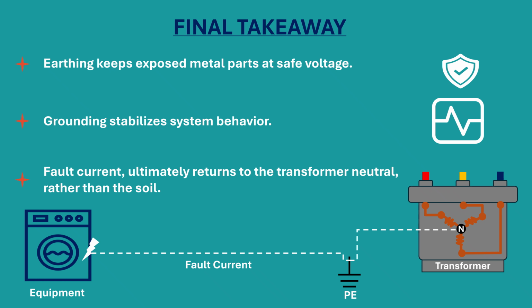In summary, earthing keeps exposed metal parts at safe voltage, while grounding stabilizes system behavior. Fault current ultimately returns to the transformer neutral, rather than the soil. Understanding this fault loop is crucial for proper design, protection coordination, and effective troubleshooting.